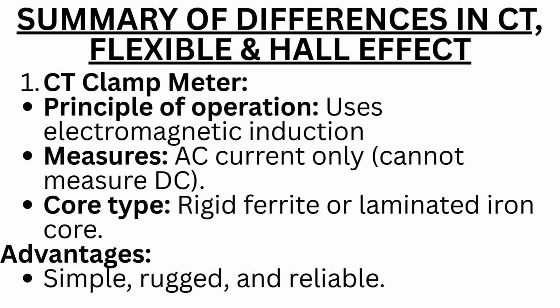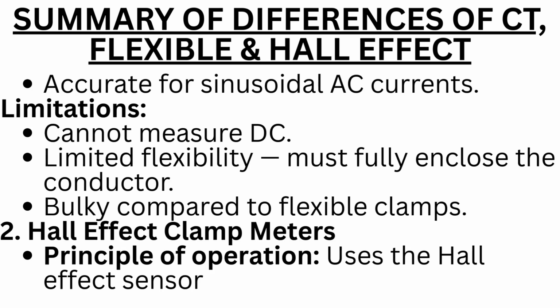Let us look at the summary of differences in CT, flexible and Hall effect clamp meters. 1. CT clamp meter. Principle of operation: uses electromagnetic induction. Measures AC current only. Core type: rigid ferrite or laminated iron core. Advantages: simple, rugged, and reliable. Accurate for sinusoidal AC currents. Limitations: cannot measure DC. Limited flexibility, that is, it must fully enclose the conductor. Bulky compared to flexible clamps.